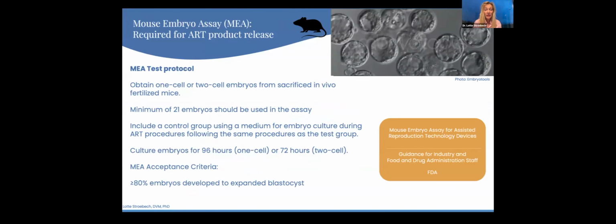So the mouse embryo assay is required for any assisted reproductive technology device that you are releasing. So there are guidelines. We are monitored by FDA through notified bodies. We show in audits our books for quality control, and every single product has gone through numerous tests along with the mouse embryo assay as a requirement for every single release.